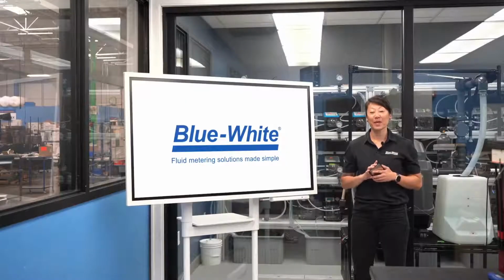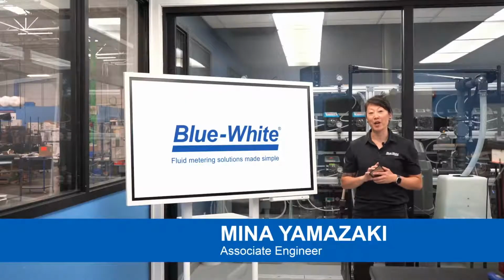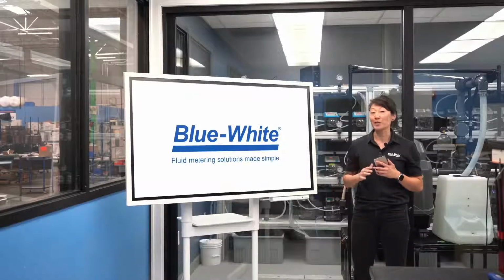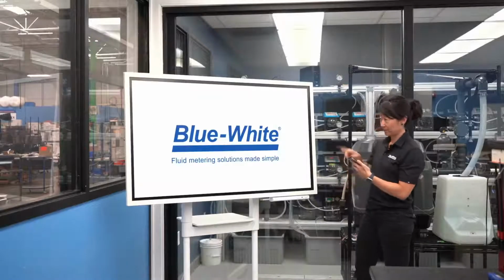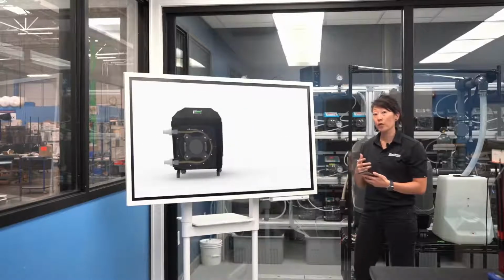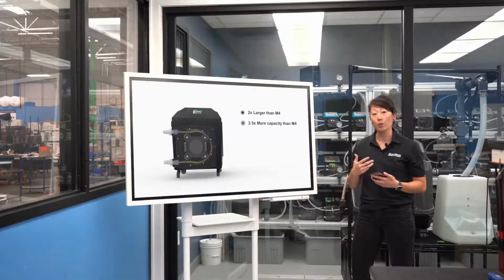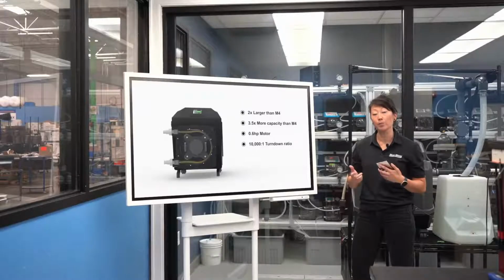Thanks, Patrick. I'm very excited to share with you the M5 peristaltic metering pump. Our objective was to make a product that performs on an entirely new level while still being familiar to the operator. Let's go over some of the main features. The M5 is 2 times larger than the M4, and its output capacity is over 3.5 times more than the M4 pump. It's equipped with a 0.6 horsepower motor and has a 10,000:1 turndown ratio, capable of flow rates up to 9 gallons per minute.